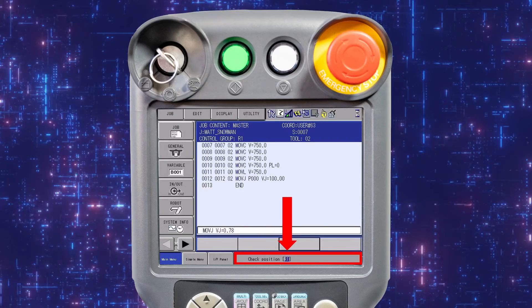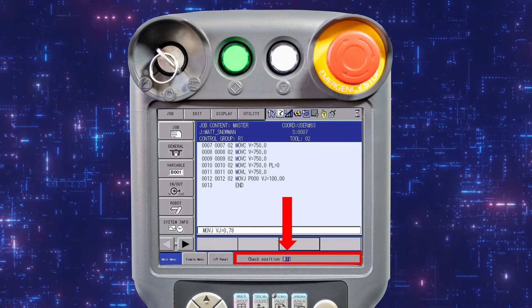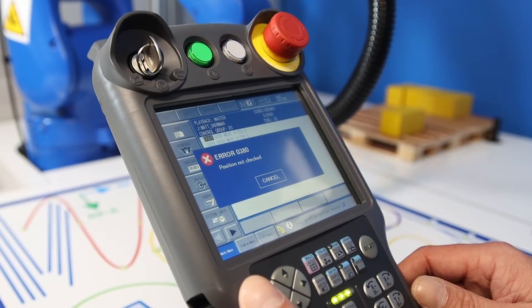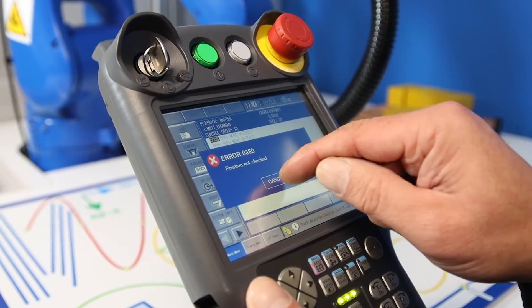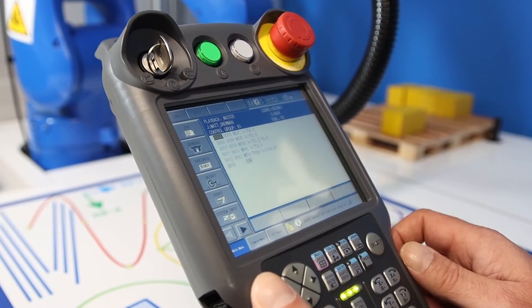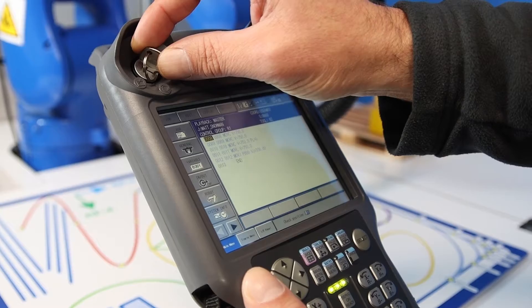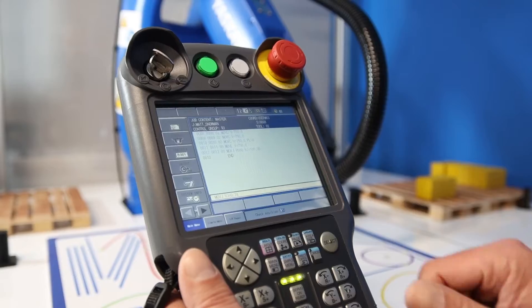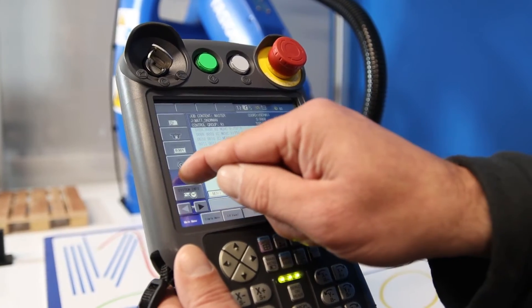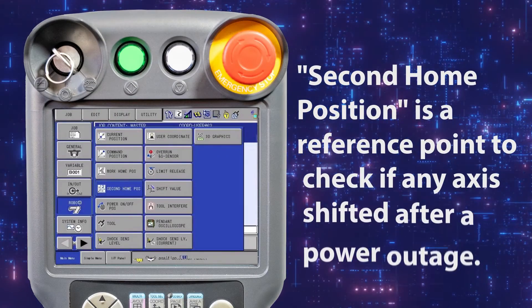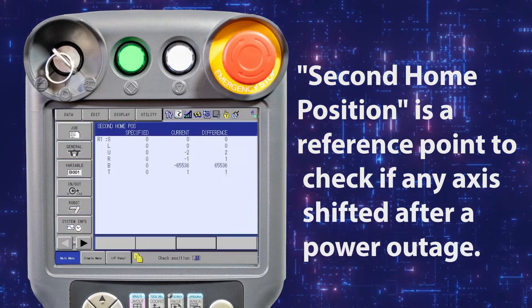While the check position message is displayed, it is not possible to return the system to play or remote. To recover the system while in teach mode, open the robot menu and select second home position.